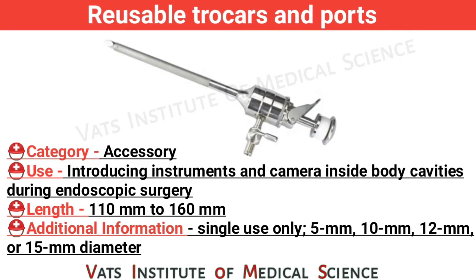Reusable trocars and ports. Category: accessory. Use: introducing instruments and camera inside body cavity during endoscopic surgery. Length: 110 mm to 160 mm. Additional information: single use only, available in 5 mm, 10 mm, 12 mm, or 15 mm diameter.